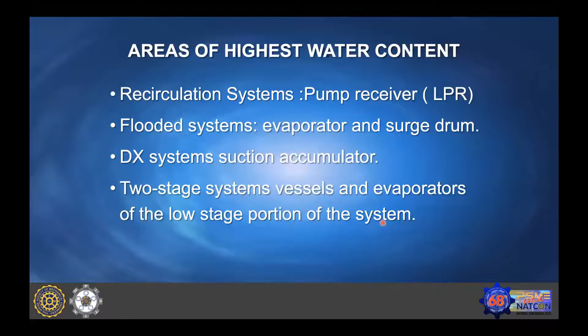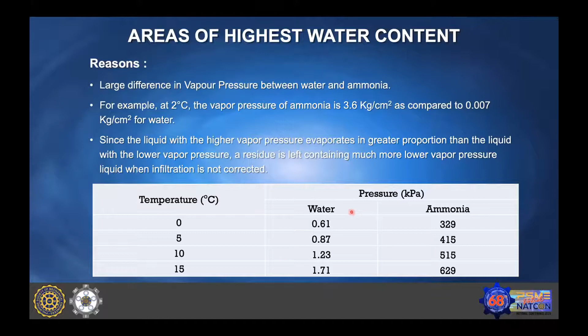The main reason is that there is a huge difference between ammonia and water in vapor pressure. For example, at 2 degrees centigrade, the vapor pressure of ammonia is 3.5 kg per square centimeter, whereas water is 0.007 kg per square centimeter. So at that pressure the ammonia evaporates, water does not evaporate and remains in liquid form, and it starts accumulating on the low pressure side. At 0 degrees centigrade, water vapor pressure is 0.61 kPa, as against ammonia at 329. At 15 degrees centigrade, water is 1.71 and ammonia is 629. You can see at different temperature conditions, water vapor pressure is very low. So even though the ammonia gas is evaporating due to the heat from the heat exchanger, the evaporator side, water will not evaporate and will remain in liquid form.